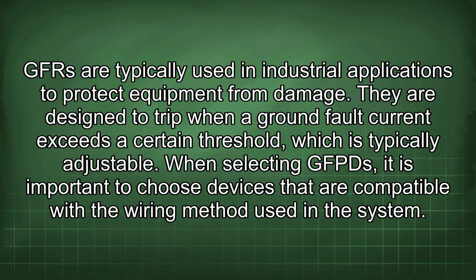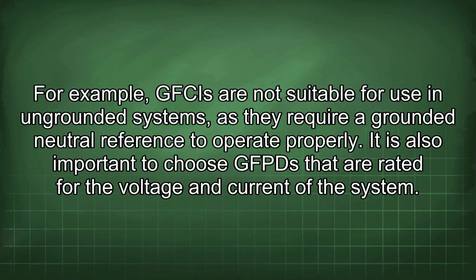When selecting GFPDs, it is important to choose devices that are compatible with the wiring method used in the system. For example, GFCIs are not suitable for use in ungrounded systems, as they require a grounded neutral reference to operate properly.